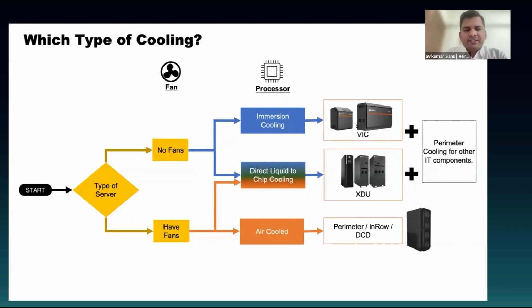So any servers which have fans, then it has fans and no fans. If it has fans, then it is air cooled, we can say air cooled servers, and we have to use air cooled cooling systems. If the system has no fans, then we can use it as immersion cooling, and we can also use it as DCL, direct to chip.